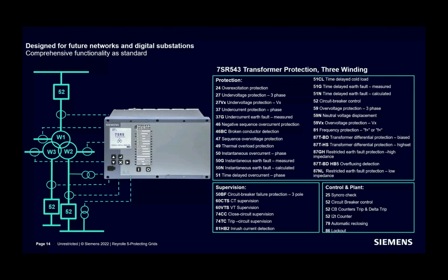Now, including all the functions and features of its 2 winding variant, 7SR543 devices provide comprehensive protection for 3 winding transformers. So the relay also provides differential protection for auto transformers. 87GH and 87NL, meaning restricted earth fault protection, low impedance and high impedance, can be applied for all 3 windings at the same time and individually.